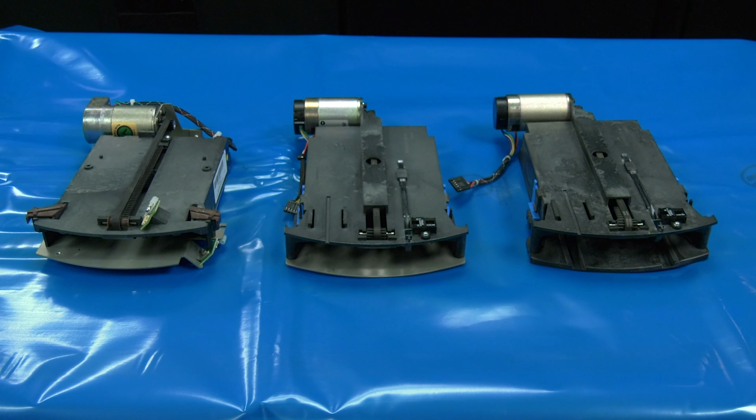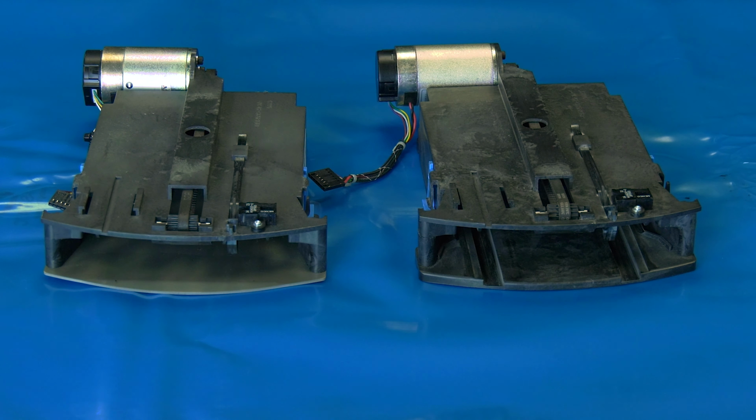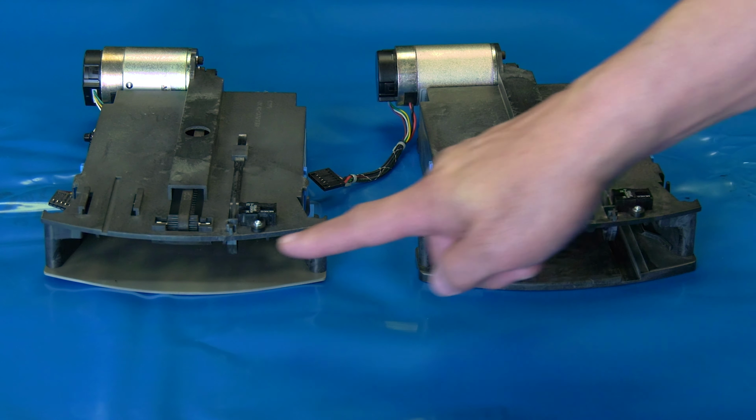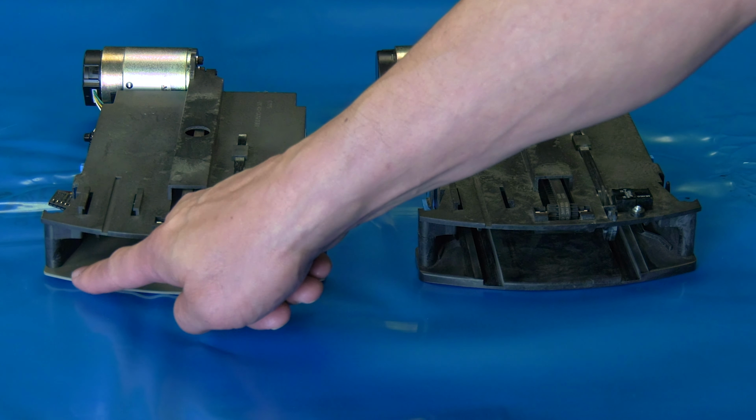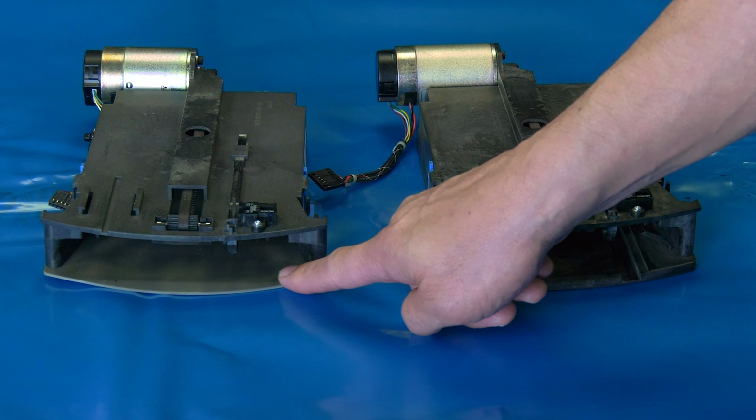There are 3 different gripper types for this library. They are old-style LTO, universal, and high density. The old-style LTO is very rare and we do not sell it on the Rocket Platform website. If you have one of these style grippers and need support, please contact us directly at support@therocketplatform.com. For this replacement, we will be showing you how to do it using a high density or HD style gripper, but the procedure is the same for the universal gripper as well.